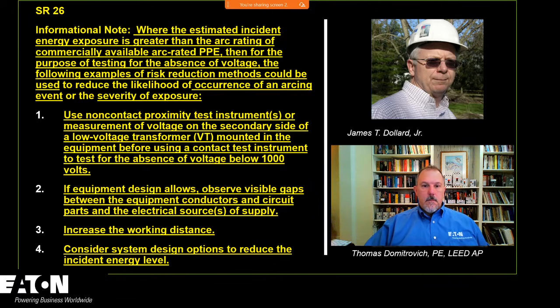increasing the worker distance. Remember, when you cut the distance in half, I've got exposed energized conductors and circuit parts. If I cut the distance in half, I increase my exposure by 400%. If I double the distance, it goes down to 25%. Right. So factor of 4. But the big one here, Tom, the one that I like the best, is to consider system design options when you're building that system to reduce the incident energy level. You want to comment on that?